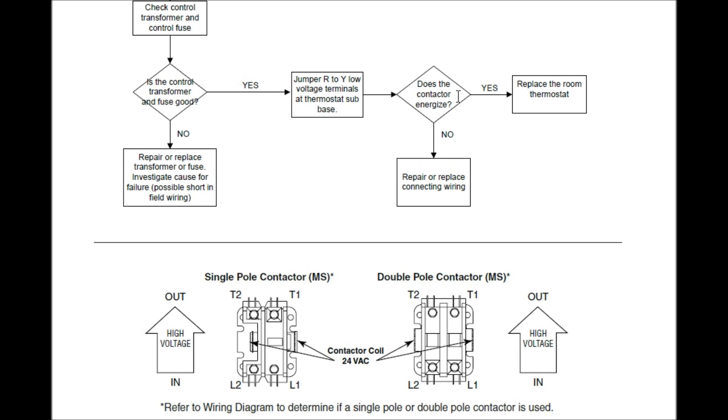Does the contactor energize? No. Repair or replace connecting wiring. That's where we need to backtrack and we need to find out whether or not we've got a short in the wire or something.